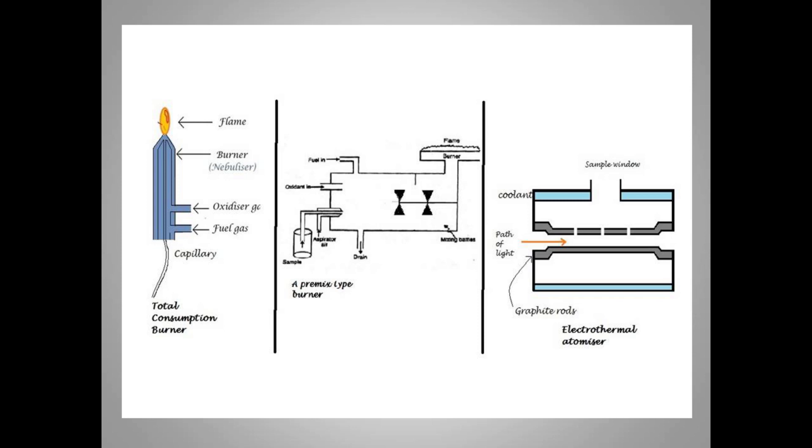In short, the first burner, total consumption burner, has three channels: the capillary through which sample enters, the fuel, and the oxidizer. All three combinations meet in the flame directly. The next is the premixed type of burner, where first the fuel, the oxidizer, and the sample get premixed and then reach the burner. The third burner is the graphite furnace. It has the graphite rod which are electrically heated. The sample enters through the window and this burner works in three stages.